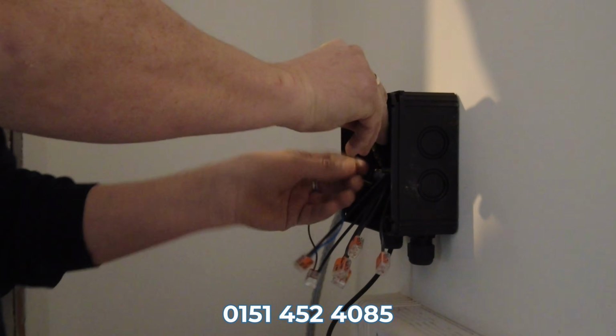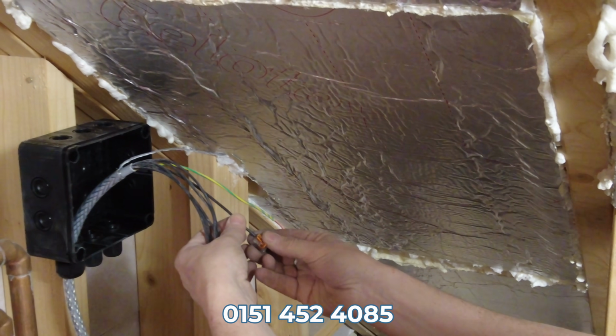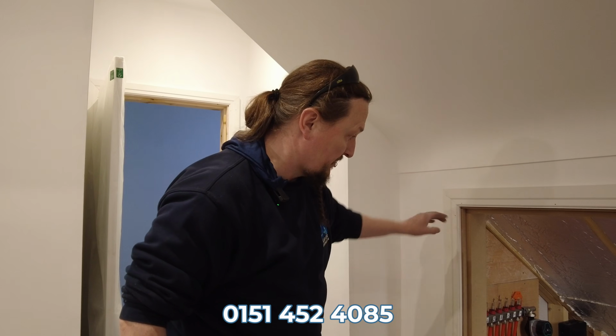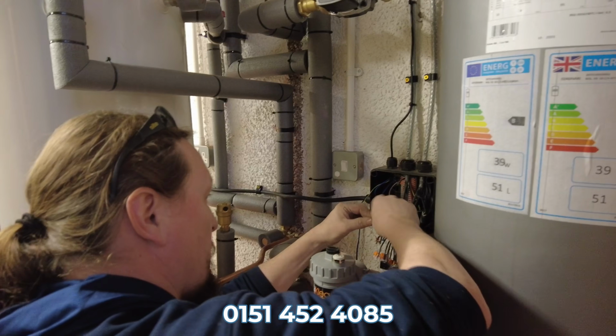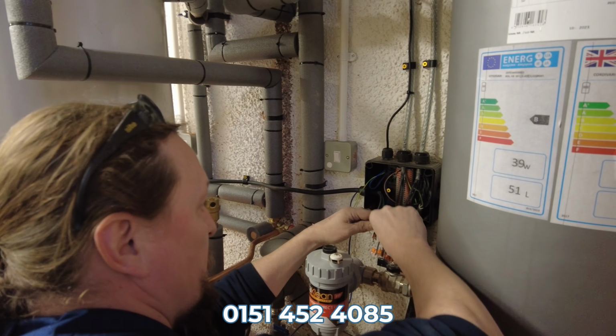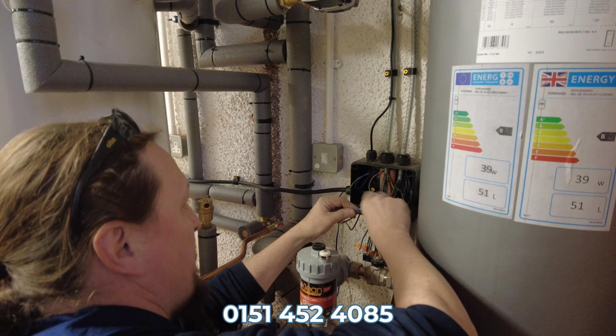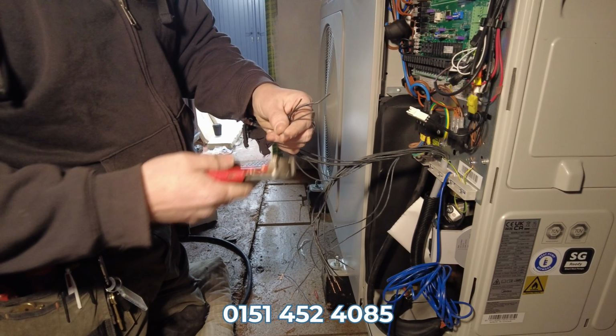Later, the heating engineers are going to fit a Heatmiser system that allows control by area, but for now we're just going to have it so the water turns off and runs all of the underfloor heating on the upstairs and all on the downstairs for our testing purposes. So we're currently connecting all the cables at a junction box in the garage, and then we'll go on to putting the cables into the heat pump.